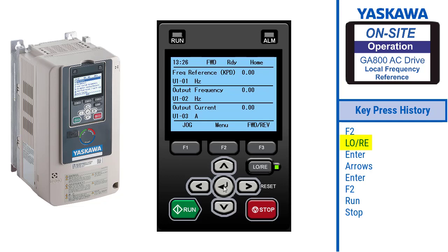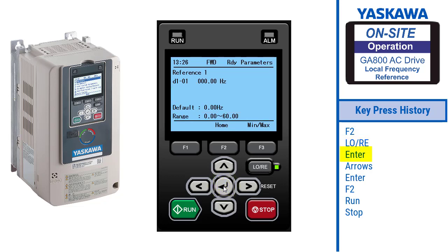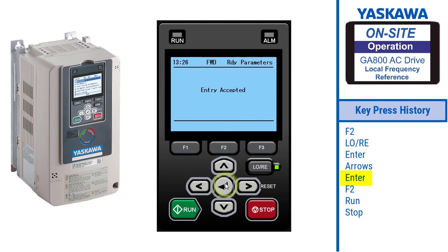Press Enter. The keypad will change to the d1-01 parameter screen. Using the arrows, change the reference frequency to 10 hertz. Press Enter. The drive will display entry accepted.